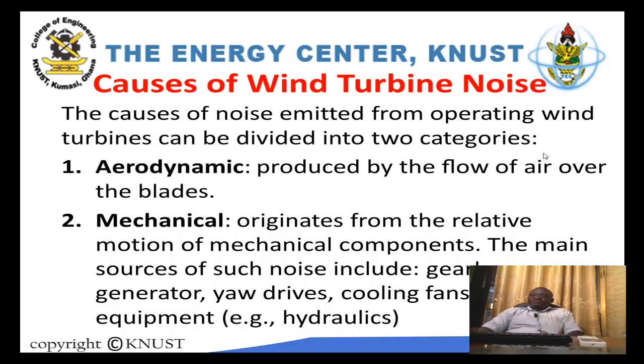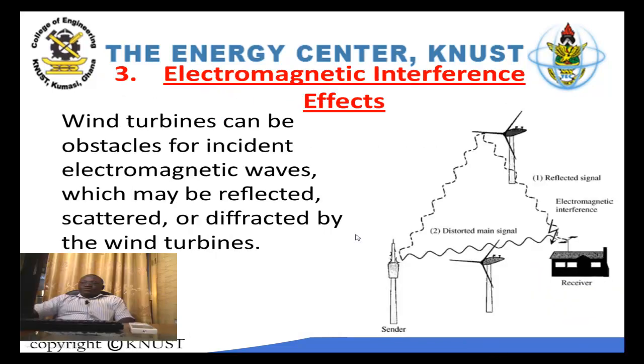There are some causes of wind turbine noise. We have aerodynamic causes and then we have mechanical causes. Aerodynamic causes are produced by the flow of air by the blades — how the blades interact with the air. Then there is mechanical noise that originates from mechanical components within the turbine: the gearbox, the generator, the yaw drives for turning the turbine to face the wind direction, and some other auxiliary equipment like the hydraulic system. They all produce sound, and those sounds are categorized as the mechanical sounds of a turbine.